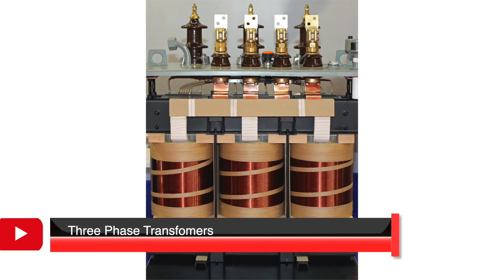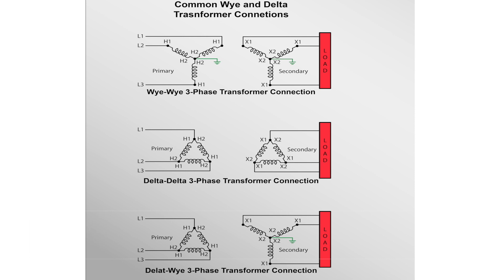Let's now go over three-phase transformers. Three-phase transformers are used to transmit high voltages in three-phase systems. These transformers are connected in three-phase Y, delta, or a combination of both. These two names come from the way the windings are connected inside the transformer. There are two types of ways the secondary distribution is commonly used. They are the three-phase three-wire system and the three-phase four-wire system. In both of these systems, the secondary voltages are the same for all three phases.